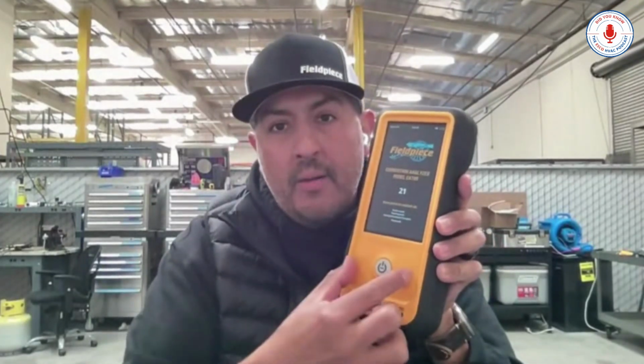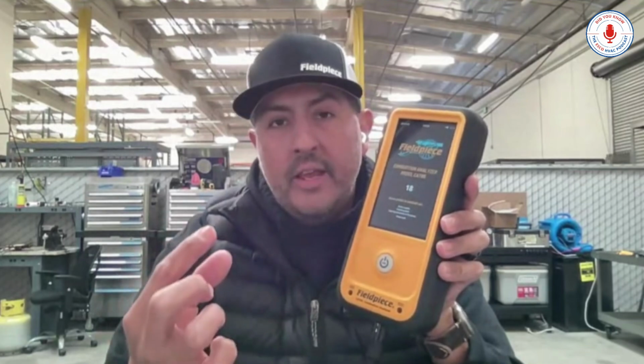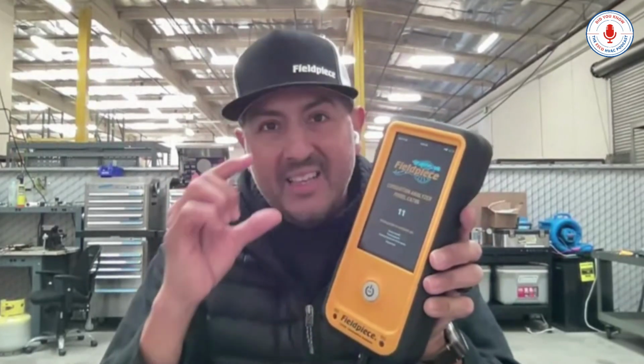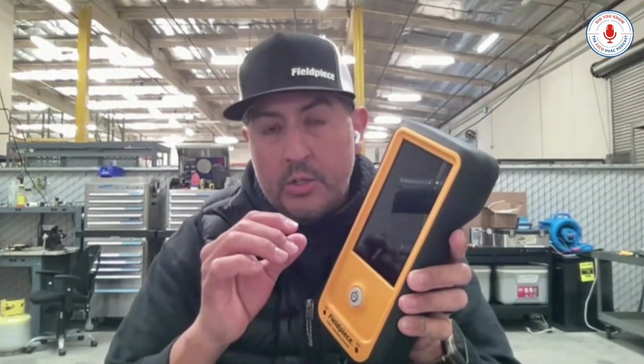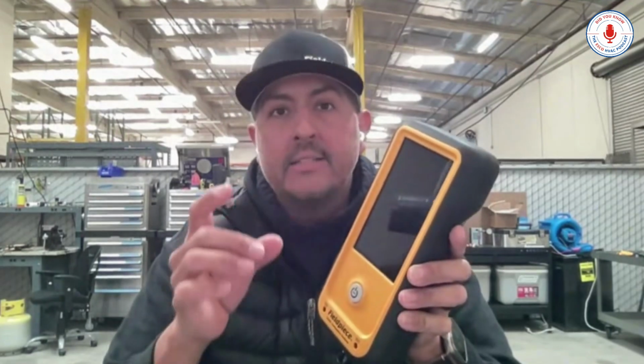Because of that, we're able to provide the contractor a 4-year sensor life warranty, so their sensors last 4 years rather than 1 or 2. When the day comes that they do have to replace the sensor, it's completely field replaceable - there's a little door panel on the bottom that pops out, you unplug the sensor, plug in the new one, and your tool is set up and calibrated because the calibration data lives on the actual sensor. That's one example of how the modernization of combustion analysis allows the technician to lower overall cost of ownership while ensuring accurate readings on these appliances every time.